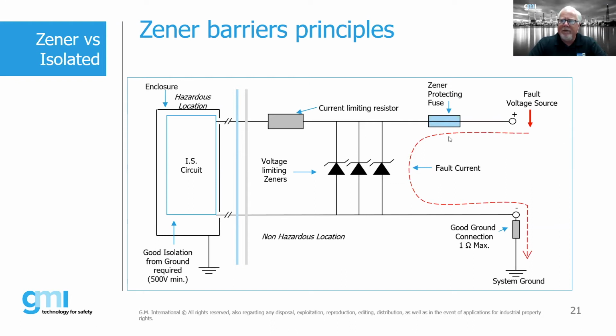So if we have a fault condition, think of the Zener diodes like an overflow on a dam, where all of a sudden the water becomes too high and we have to allow that water to escape. Therefore, those Zener diodes open up. As the voltage increases, the Zener diodes open up and allow that excess energy to go to a system ground.